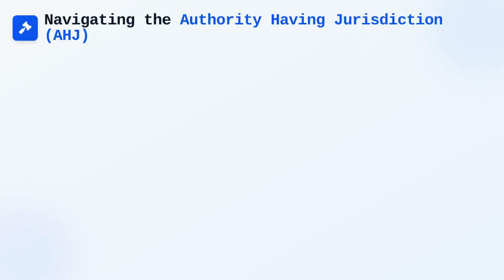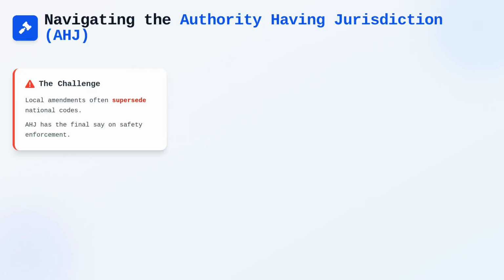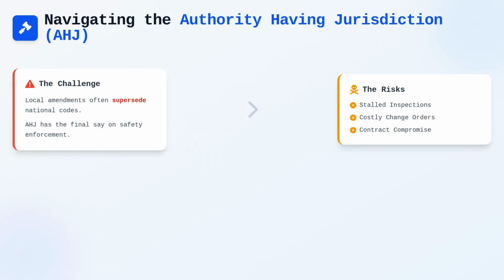The primary challenge in modern design is the role of the authority having jurisdiction. You may encounter a scenario where a local municipal amendment is more stringent than the national electrical or building code. Experienced designers understand that the authority having jurisdiction has the final say on the enforcement of safety protocols on a job site.